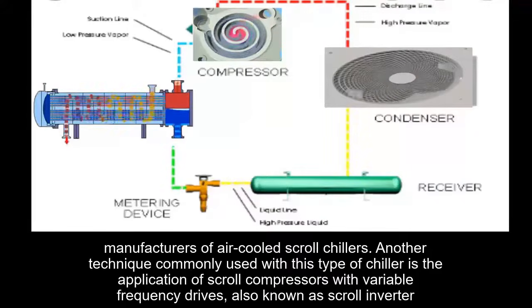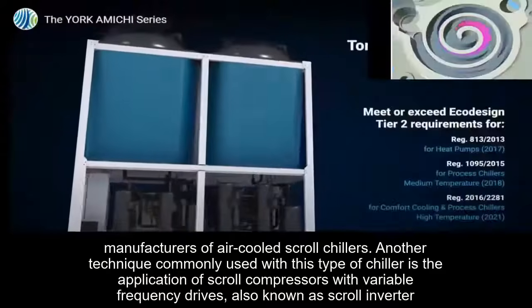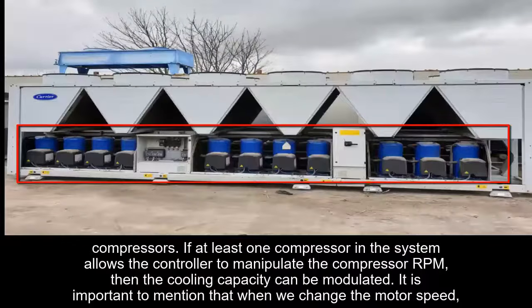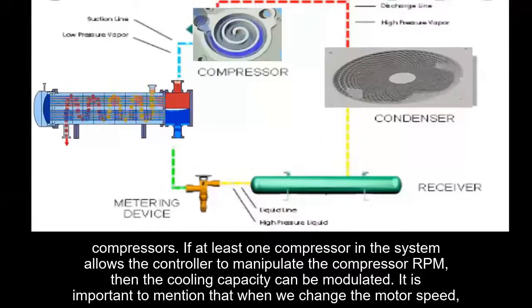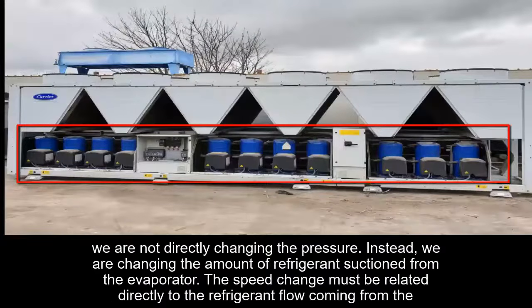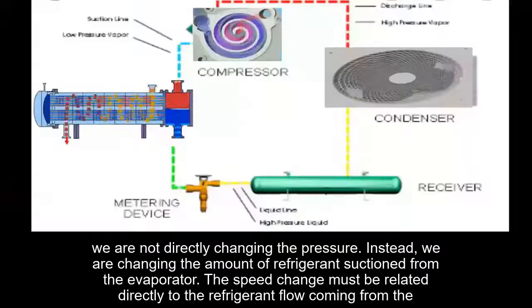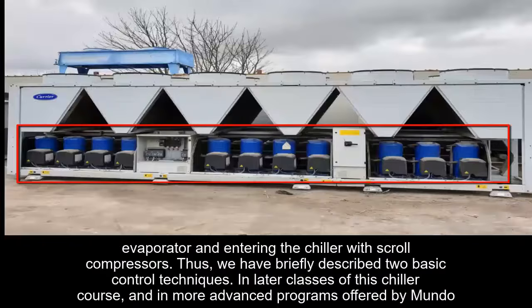Another technique commonly used with this type of chiller is the application of scroll compressors with variable frequency drives, also known as scroll inverter compressors. If at least one compressor in the system allows the controller to manipulate the compressor's RPM, then the cooling capacity can be modulated. It is important to mention that when we change the motor speed, we are not directly changing the pressure. Instead, we are changing the amount of refrigerant suctioned from the evaporator. The speed change must be related directly to the refrigerant flow coming from the evaporator and entering the chiller with scroll compressors. Thus, we have briefly described two basic control techniques. In later classes of this chiller course and in more advanced programs offered by Mundo Chiller, we will study these and other thermal load control strategies in greater detail.